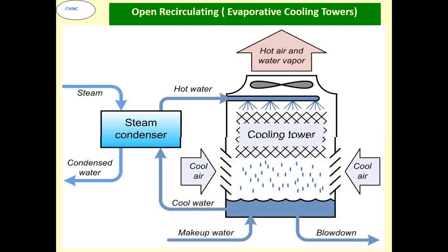The third system, which is becoming the most common, is the evaporative cooling tower system. In this system, we take water from the source and use it for cooling down the steam. Not only steam, any other process can also be cooled. The heated water is then passed on to the cooling tower, where it is cooled, and maybe some little makeup is added, and something is taken out as blowdown, which is sent to the effluent.